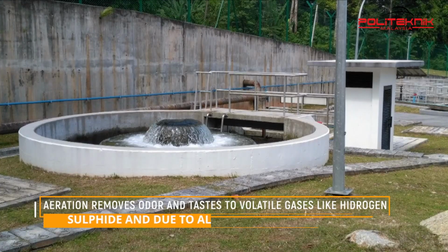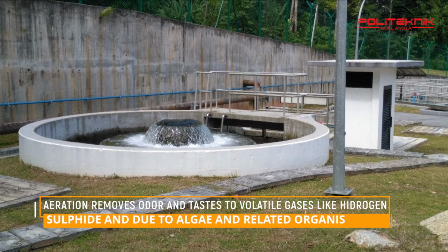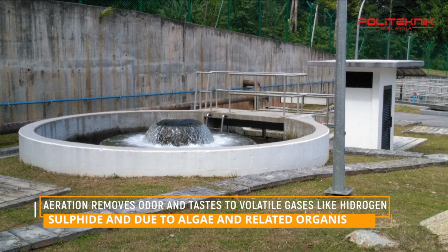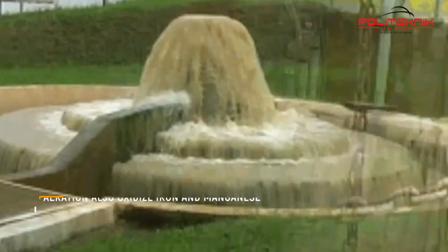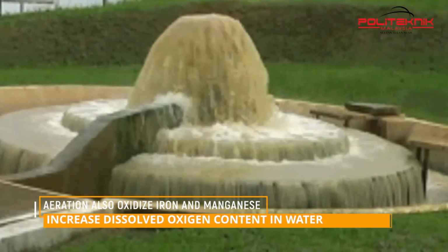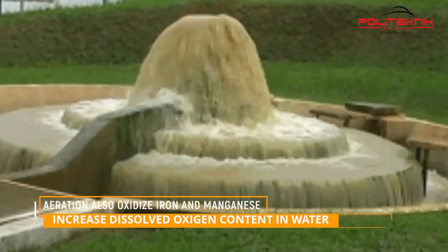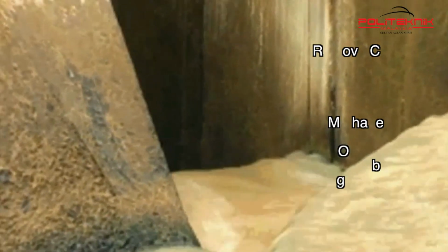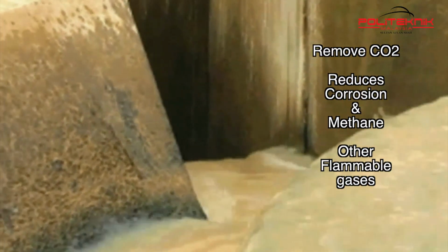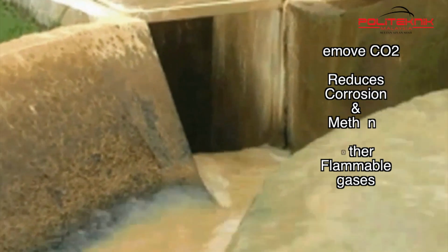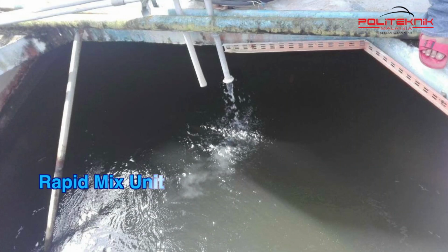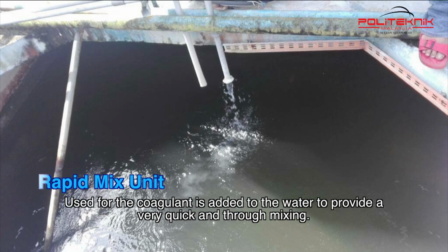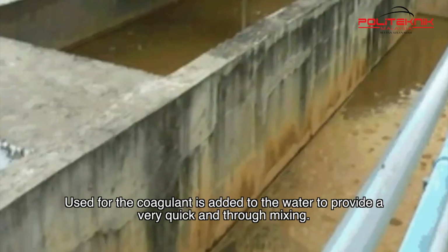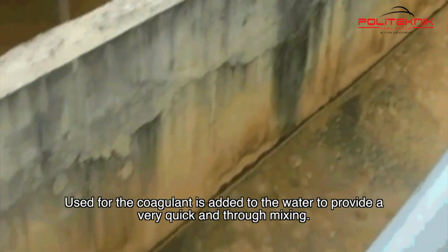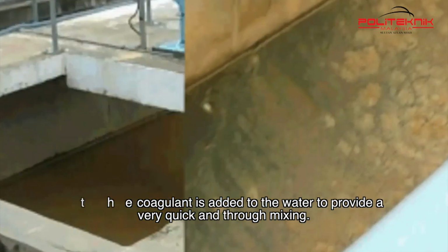Aeration removes odor and taste due to volatile gases like hydrogen sulfide and due to algae and related organisms. Aeration also oxidizes iron and manganese, increases dissolved oxygen content in water, removes carbon dioxide, and reduces corrosion and methane and other flammable gases. A rapid mix unit is usually used where the coagulant is added to the water to provide a very quick and thorough mixing. Examples of coagulants are aluminum sulfate, ferrous, and lime.